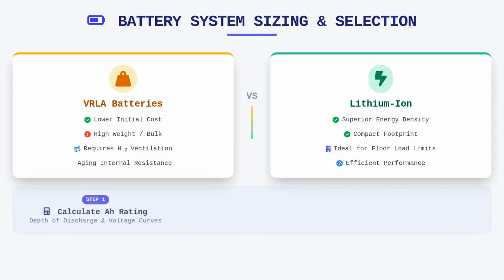Lithium-ion alternatives offer a much higher energy density and a smaller physical footprint, which is beneficial when floor load ratings are restricted. When calculating the required amp-hour rating, you must factor in the depth of discharge and the manufacturer's end-of-discharge voltage curves to ensure the runtime requirements are met under full load.